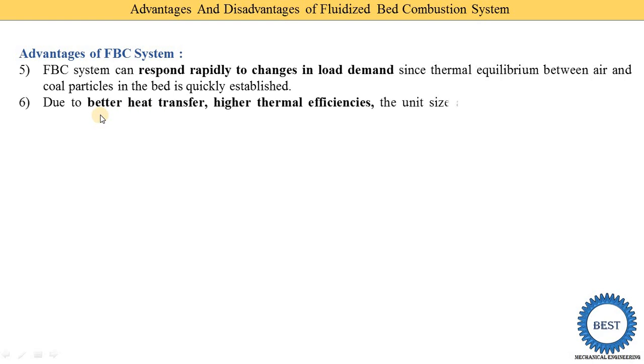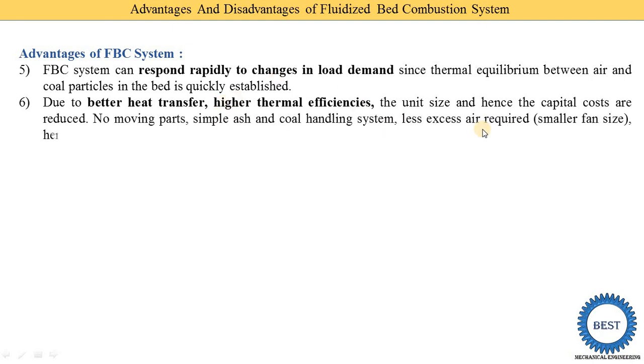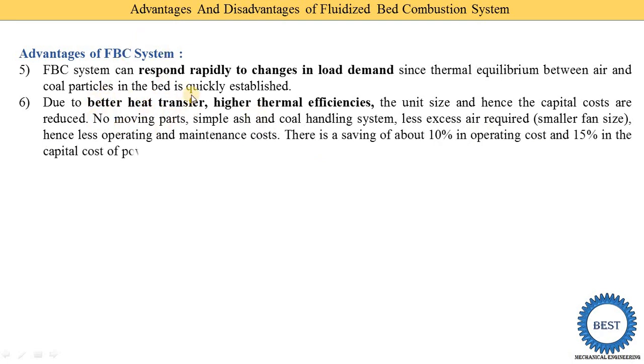Due to better heat transfer, higher thermal efficiency is achieved and the unit size is reduced. This is because Q = mCpΔT and the required mass — which depends on the heat transfer area — is lower when heat transfer is better. Therefore the capital cost is also reduced. Additionally, there are no moving parts in the coal handling system, making it simpler.